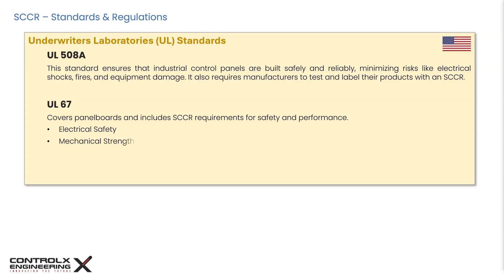UL 67 is a safety standard covering electrical panel boards, also known as distribution boards. It specifies that panel boards must be marked with the appropriate SCCR, which is essential for proper installation and coordination with other electrical equipment. UL 67 also covers design and construction aspects including insulation, wiring methods, grounding, and overcurrent protection to prevent electrical shocks and fires.